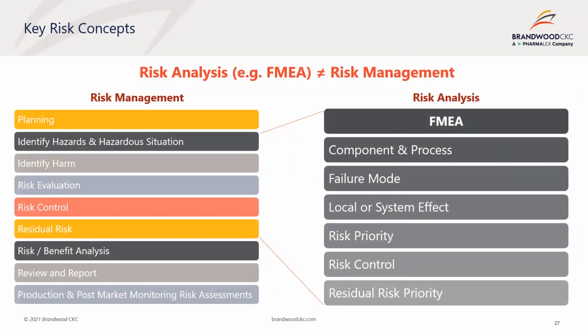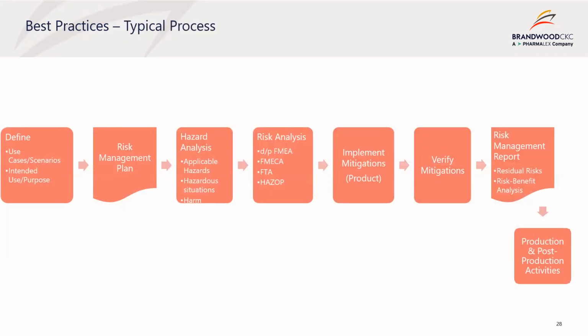A very important distinction to be made is understanding the difference between risk management and risk analysis, for example, FMEA. Risk management involves planning, identifying hazards, hazardous situations, harms, evaluating risks through risk analysis, and putting in place controls to mitigate. It also involves determining residual risks, risk-benefit analysis, reviewing and reporting. After the product is developed and released, risks need to be assessed during production and post-market monitoring phases. Whereas risk analysis only occurs within the overall risk management framework and is not sufficient alone to cover the requirements for risk management. Lastly, I want to provide some best practices when conducting risk management activities.